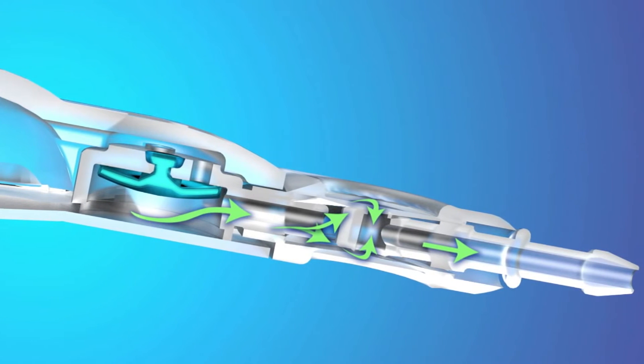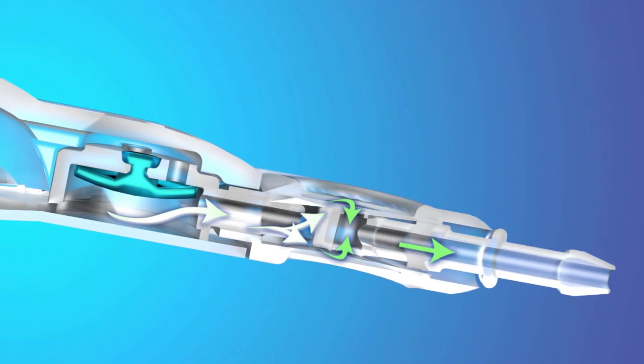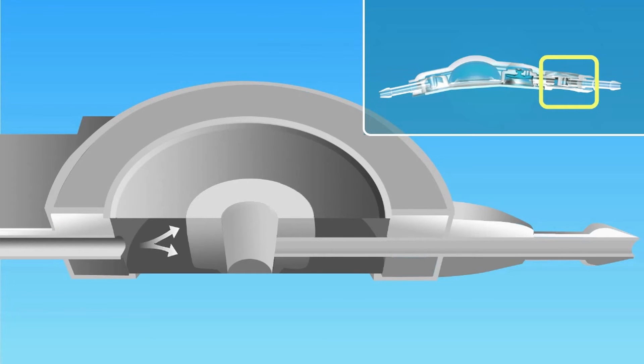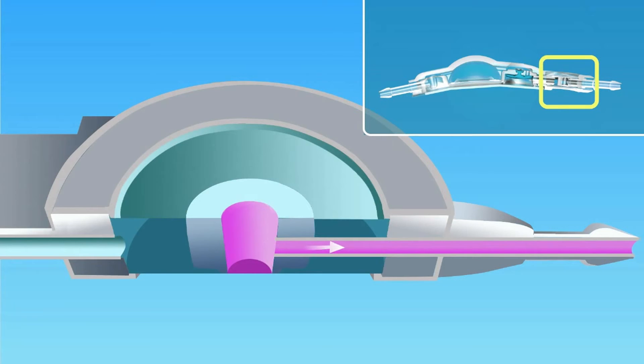After passing through the membrane valve, the CSF reaches the delta chamber. The inlet area of the delta chamber diaphragm is greater in size than the outlet drainage port, thus allowing positive inlet pressure to control the delta chamber while minimizing the effects of negative hydrostatic outlet pressure.